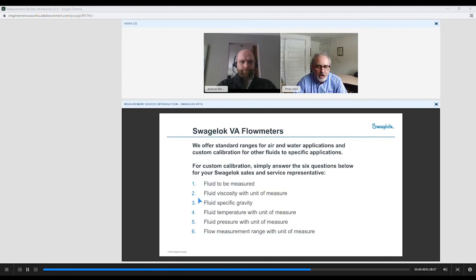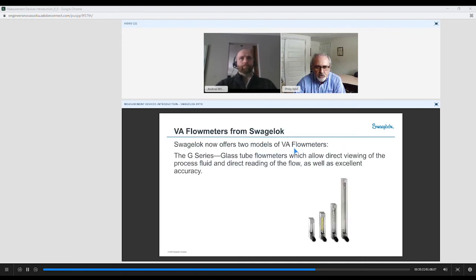So if you are looking to have a flow meter for another liquid, other than air or water applications, there are some simple questions that one of our technical reps would talk to you about: the fluid being measured, the viscosity of the fluid with units of measure, the specific gravity, temperature with the units of measure and range, fluid pressure with unit of measure, and then again, flow measurement range with unit of measure. So these are questions that we would talk to you about, or if you were working with another manufacturer, they would do the same. Most variable area flow meters are calibrated to air and water. And again, you can reach out to us and we would certainly help you with that.